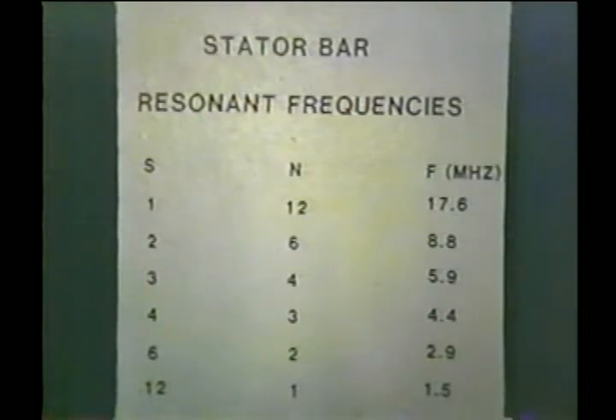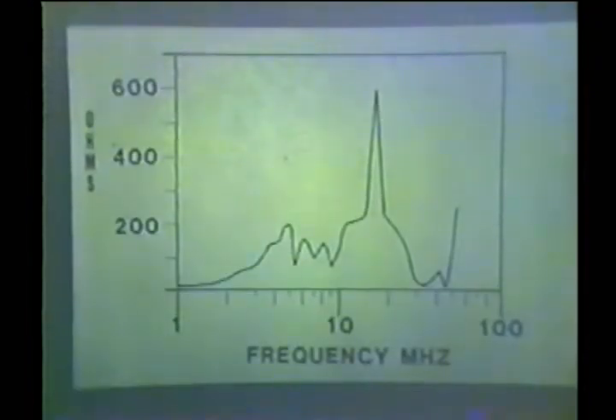Also, with the Steinmetz criteria, he said that the section in oscillation must be short when compared to the entire circuit. So in other words, where 6 stator bars produce a half wave, or all 12 stator bars in a complete circuit produce a half wave, these oscillations may not occur. And indeed, if we refer back to the impedance curve, the lower frequency oscillations either do not exist or are very small, but we have very good correlation on the others.